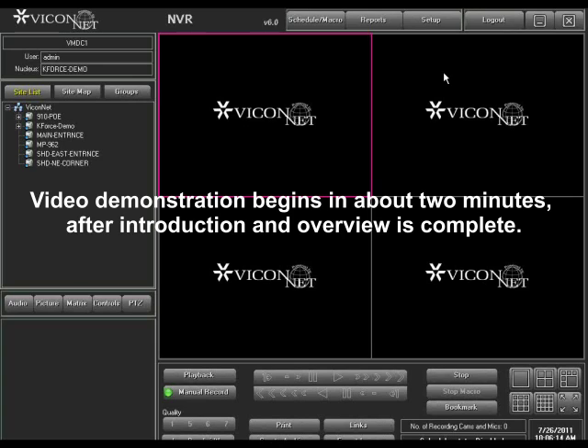We'll start off with the dry contact. Basically, some ViconNet products include the dry contact alarm. This can be from one contact and up to 16. Follow the specific unit's installation instructions on how to connect the contact. The idea being that you connect the contact to a fire system, fire alarm. You can even do it to a light switch if you wanted to. I'm sorry, a fire alarm, smoke detector, and the alarm coming in, rather, would be triggered on the system. The system would then be able to notify that that particular alarm went off, and then you'd be able to react to that alarm.